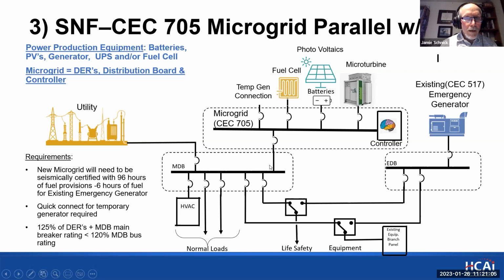705 has specific requirements about the sizing of this existing bus and the load that can be added to it. Obviously, we don't want to exceed the rating of this bus, but typically what we've seen is that could be met with little changes. The code requirement is that 120% of the rating of this bus needs to exceed the summation of the main breaker of this board and the resources available. And typically what we see is that these breakers can be downsized to meet this code requirement. So in this case, we have the microgrid.